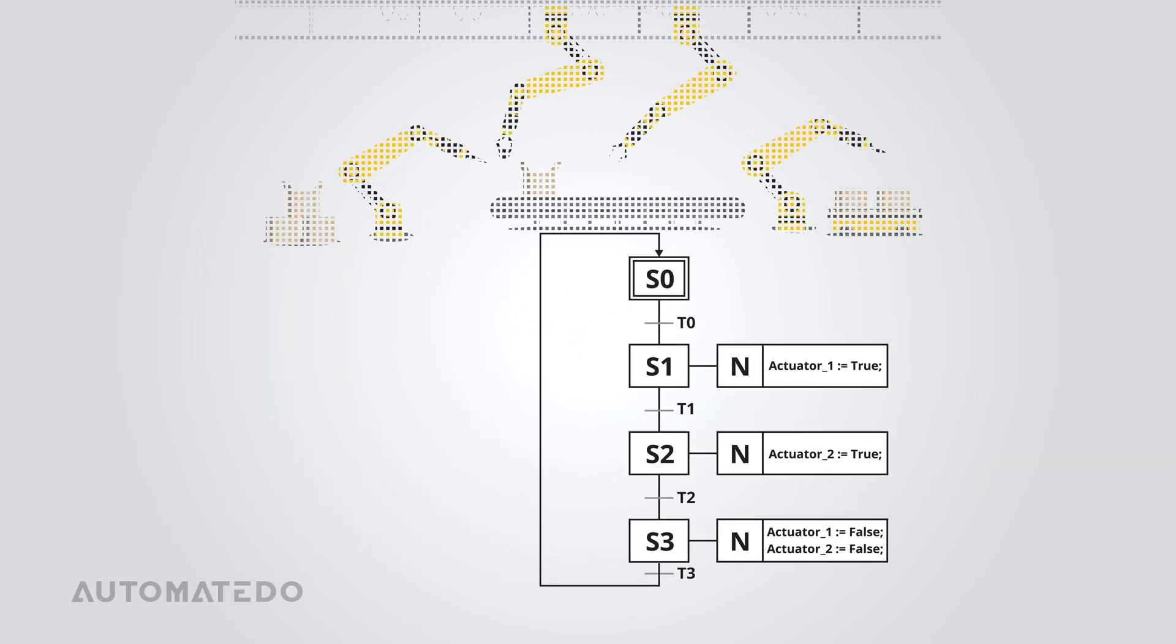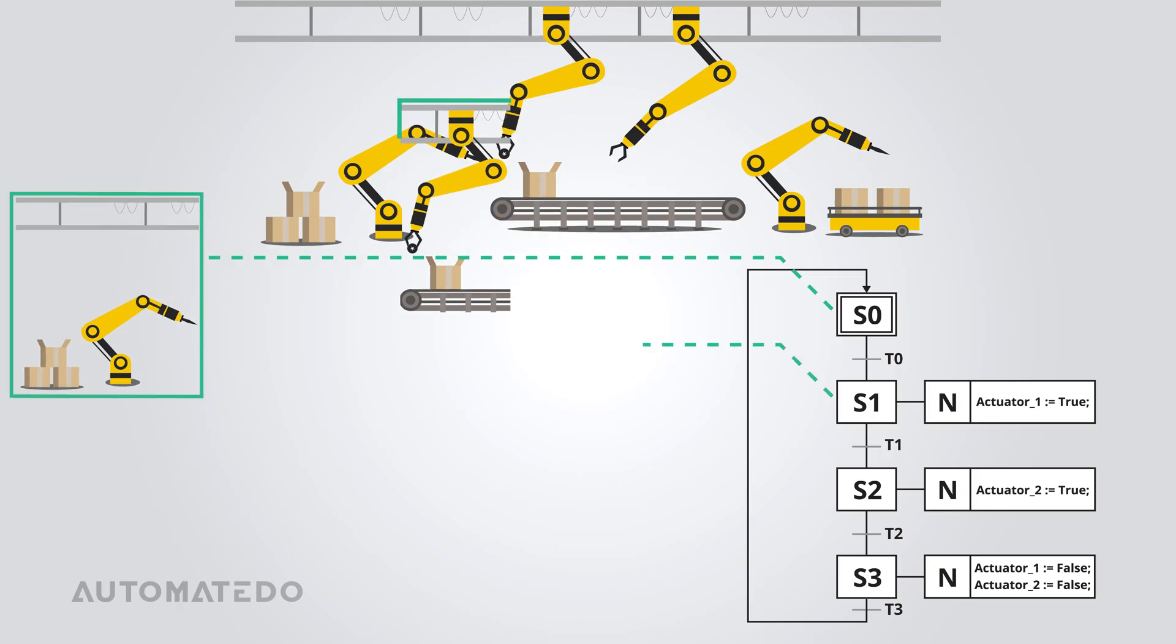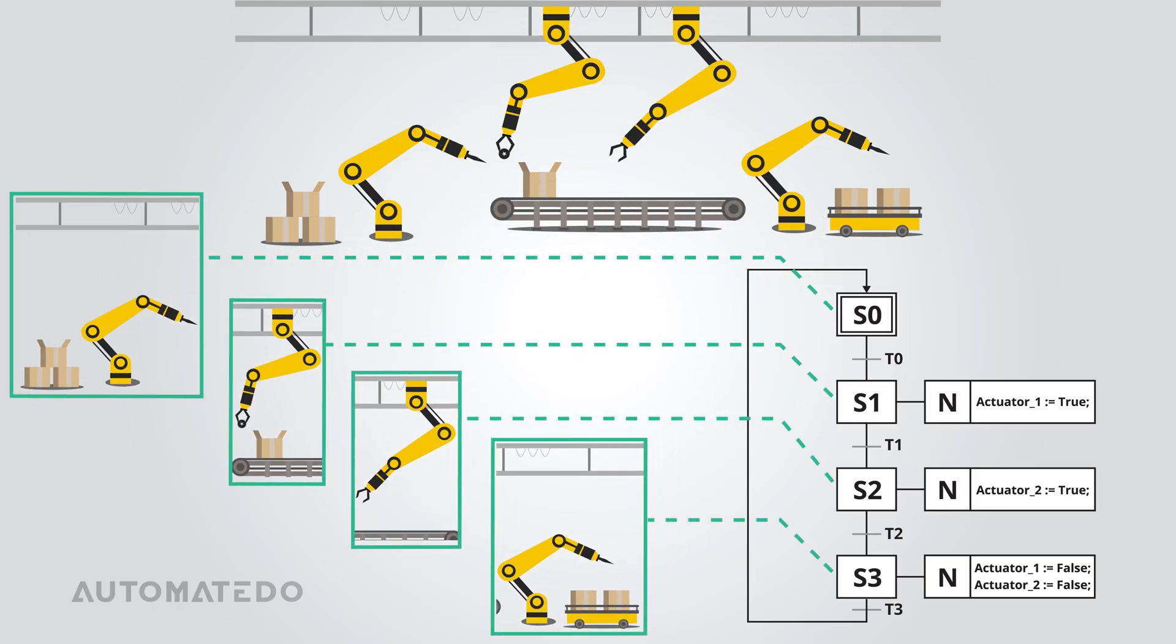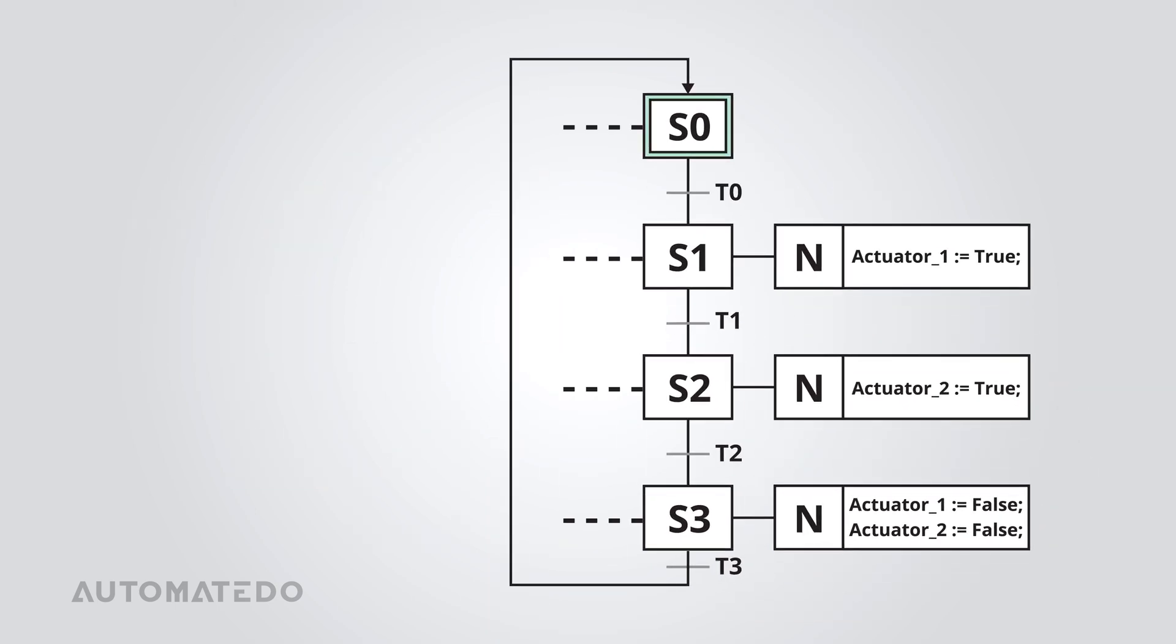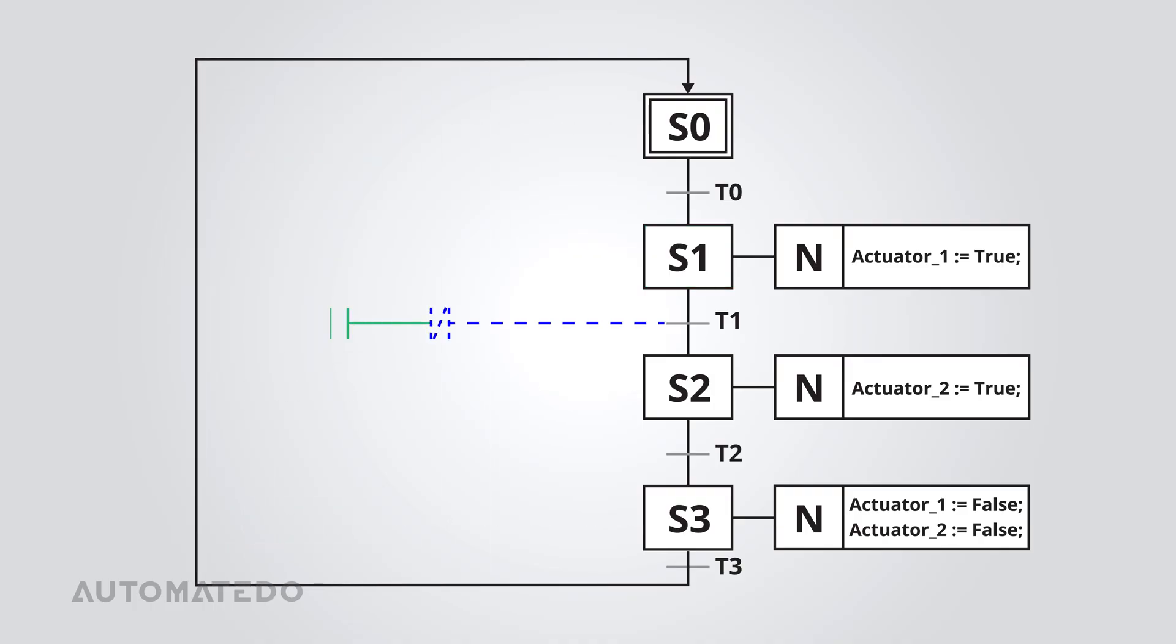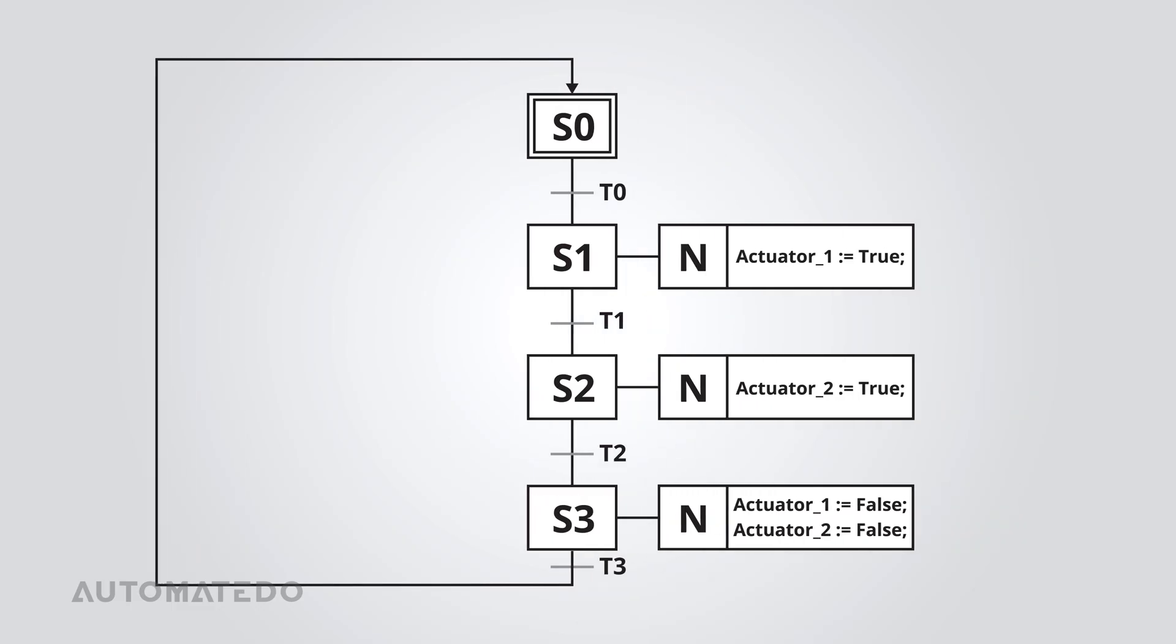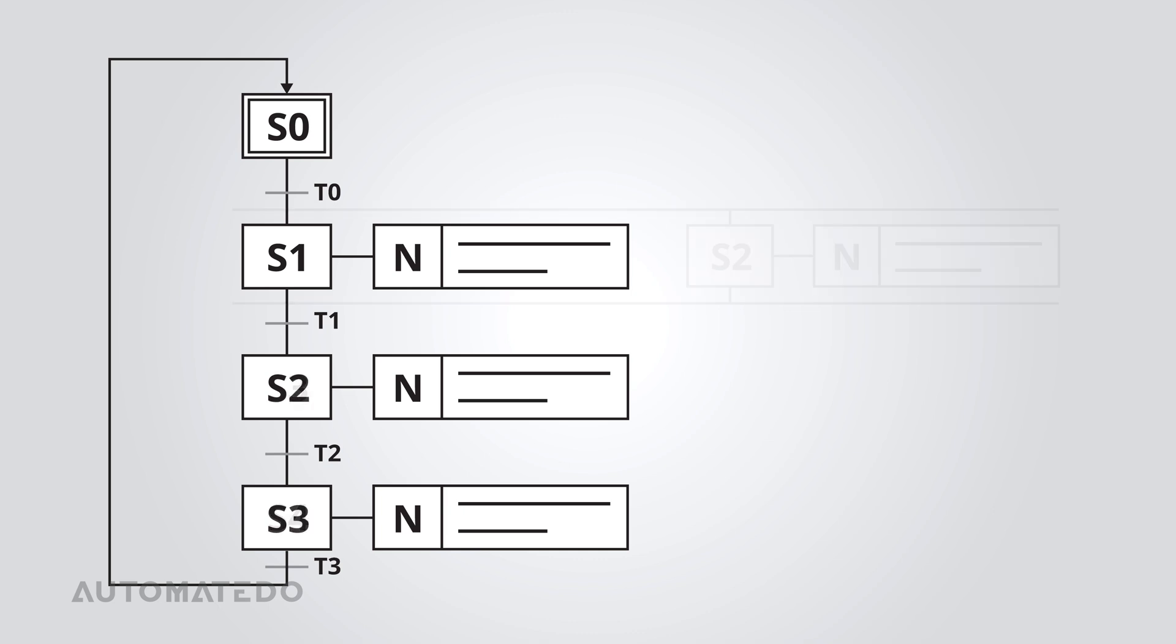However, SFC has some great advantages. First, it makes complex processes way more manageable by breaking them down into smaller, easier-to-understand steps. Another big win is how easy it is to monitor during runtime because you can visually see which step is active at any given moment. Also, SFC is a game-changer for debugging because you can directly see where a fault happens so you can pinpoint and fix the issue. On top of that, PLC development can be faster because SFC lets you reuse individual pieces of logic, reducing redundant work. And if you're dealing with parallel operations that need to sync up at some point, SFC handles that as well.